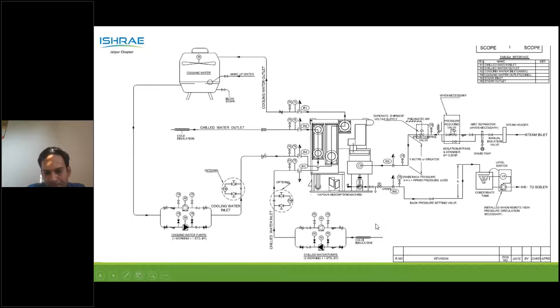Further, based on the COP, we know the COP of a machine is a parameter to analyze the efficiency of the chillers. COP, you know, is the energy output or the refrigerating effect divided by the energy input. In this case, it is the heat input. COP of single effect VAM is 0.7, double effect 1.4, triple effect 1.5 plus.